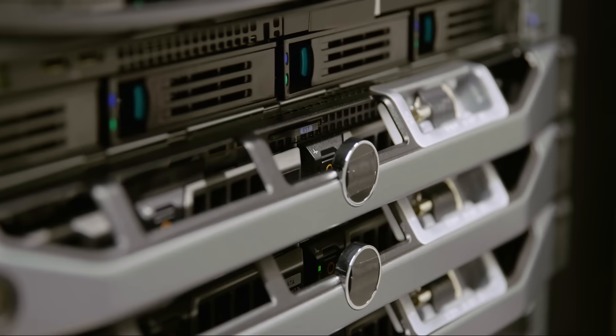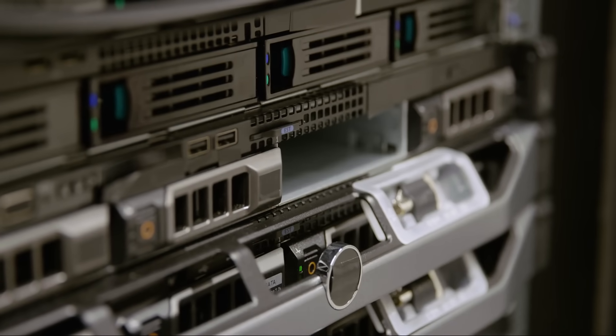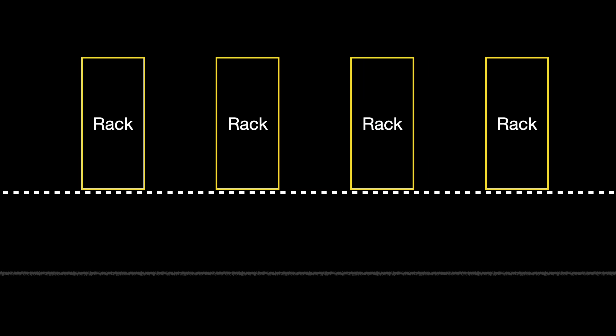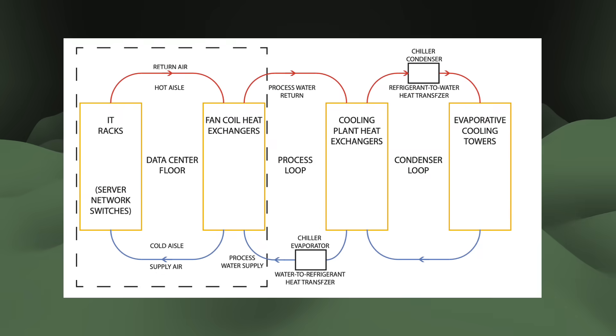Electronic equipment must be kept cool to prevent long-term damage. Hard disk drives need to be kept at about 45 degrees Celsius (113°F), while solid-state compute and storage chips have higher limits. Maintaining stable temperature and humidity is the job of the cooling system. Most data centers use a raised floor air cooling system, with racks elevated 2 to 4 feet. Cold air from the computer room air conditioner (CRAC) is shepherded into cold aisles to draw heat from servers. This hot air rises and is recollected to send to fluid heat exchangers. The most common system uses two fluid loops: a process loop and a condenser loop.